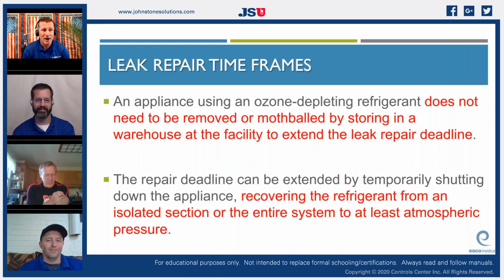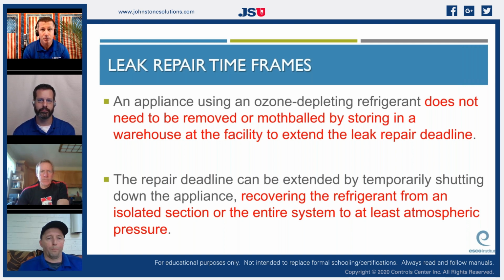So I had a rack system that was an R22. This was a two-rack grocery store, a 190,000 square foot facility. The medium temp rack on it had 11 compressors and 1,400 pounds of R22. Early in the year, it had an evaporator coil leak and lost a few hundred pounds of refrigerant. That was repaired and documented.